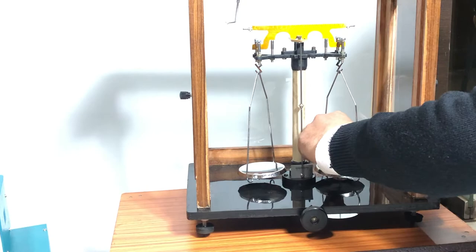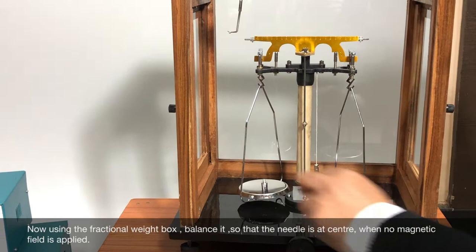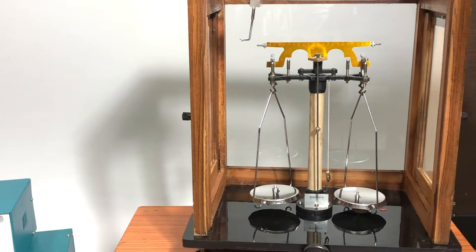Now using the fractional weight box, balance it so that the needle is at center when no magnetic field is applied.